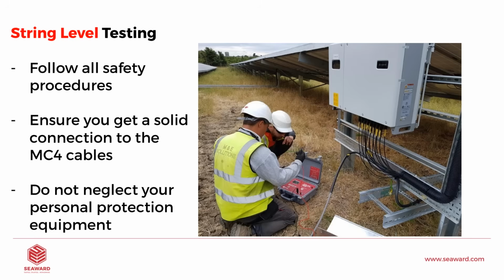String level testing is a lot safer, I find, because we're not dealing with the full combiner box. Arc flash protection is not so much of an issue. However, we should still be very careful. We can connect directly to the MC4 cables, or we can use the alligator clips to connect to the end of the PV cable. So we have 2 methods there. We also provide probes, so you can use probes into the positive and negatives.